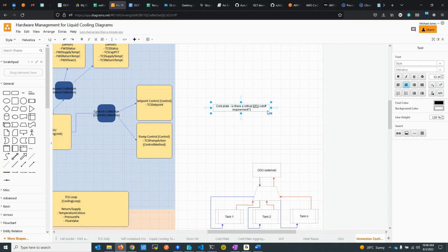Yeah, and I'm assuming none of these scenarios arrive quickly, so there should be alarms going off all over the place before you even get anywhere near those points. But just a question: will the server shut down itself? Why would we shut down the PDU? Because the server will either regulate itself if the temperature goes up and it will throttle, or it will shut down itself. So why are we shutting down the PDU for it? Because it will regulate itself.